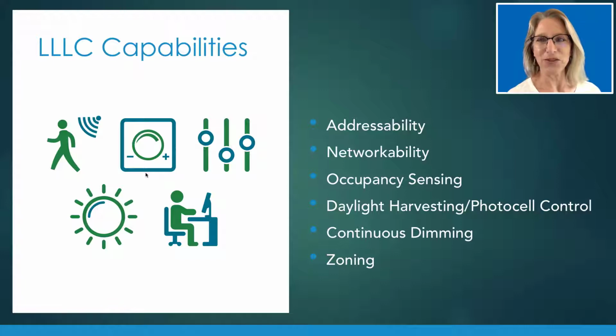So Luminaire level lighting controls enable the following features. They provide luminaire and device addressability, which is the ability to individually address each unique system device independent of electrical circuiting. They support networking of luminaires and devices so that each addressed fixture, switch, or sensor is capable of individually communicating digital data between these devices in the room or space. They include occupancy and daylight sensing controls and automatic light level continuous dimming, which is progressive, gradual light level changes perceived as smooth adjustment as opposed to step dimming. They also support flexible zoning so that luminaires may be configured to form unique, reassignable control zones.